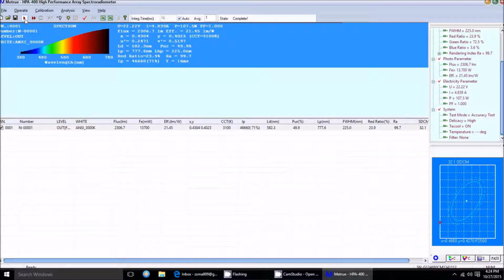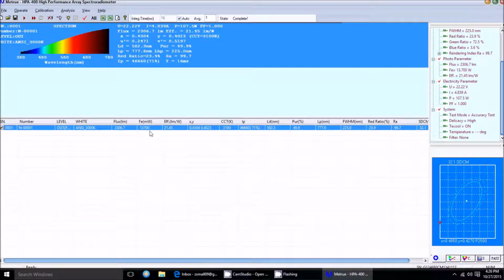So hopefully my measurement here will be the same as my standard lamp once it's done. Okay, so this is our measurement of the calibration lamp. Our flux here is 2306.7. Our calibrated standard lamp is calibrated to a total luminous flux of 2305.6, so that is under 1%. That is a very good calibration. And that is it for the installation of an integrating sphere.